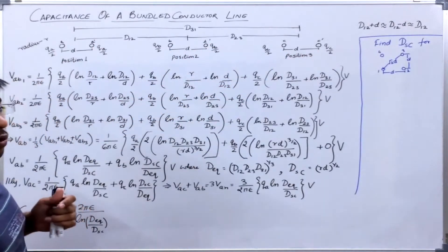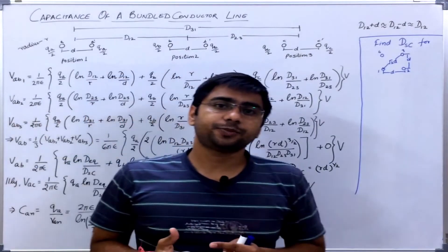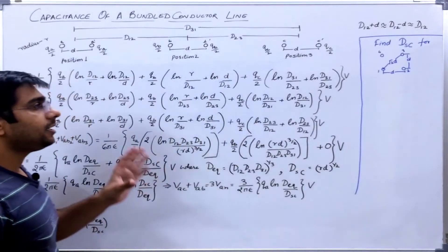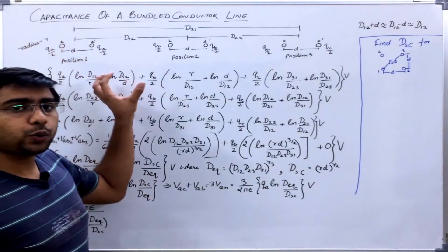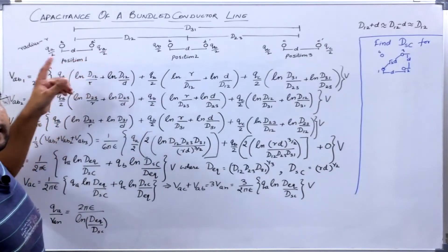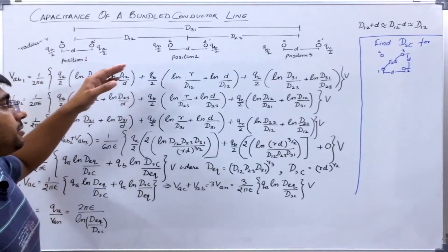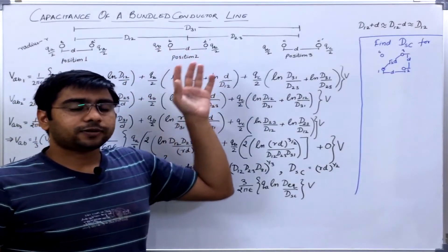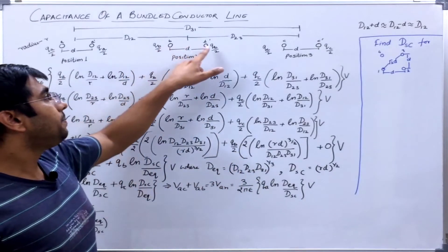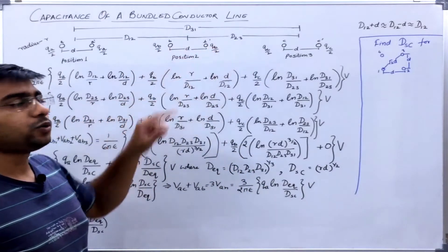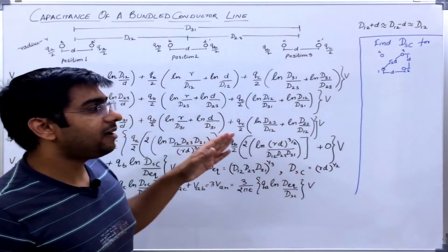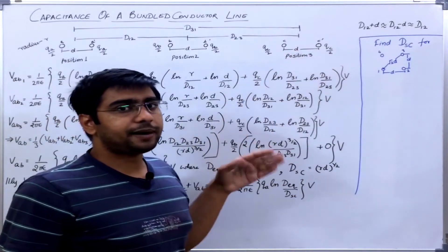We are also assuming that the charge distributes equally between the same phase conductors. If there is total charge QA on phase A, then A and A dash will carry equal charge, that is QA by 2 and QA by 2. Similarly, if phase B carries total charge QB, then each strand will carry QB by 2. Similarly, if phase C carries total charge QC, it will be equally divided between the two strands as QC by 2.